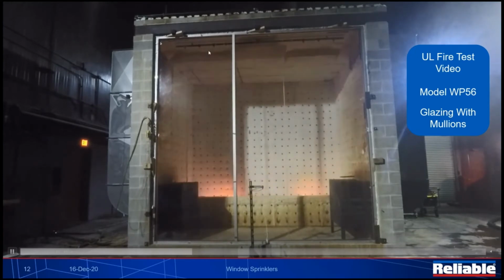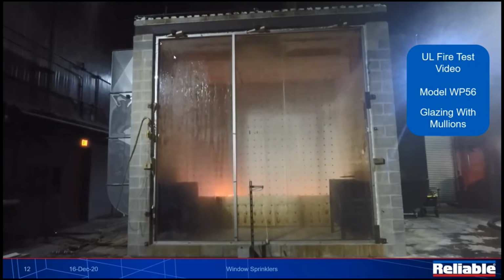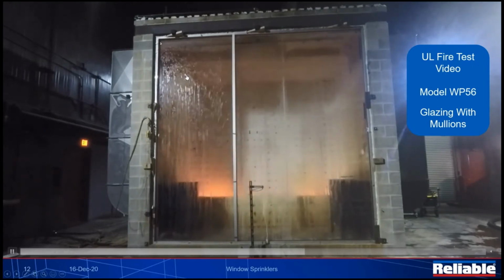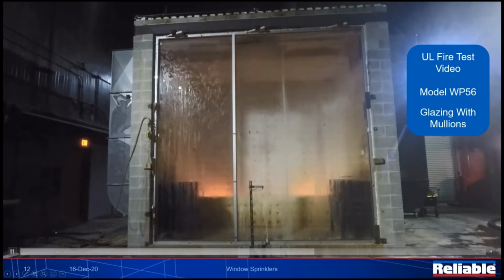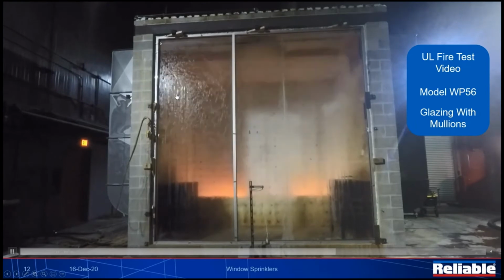right here. And it does take a few minutes for us to get our temperature activation here for our sprinklers. And there we go, we get our activation. Now what I want to do is focus your attention right here. And you can see that we start flowing water up at the top, and it takes time for these dry spots to fill in, but eventually they are going to fill in.